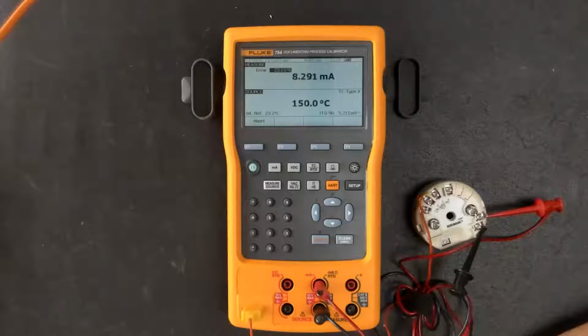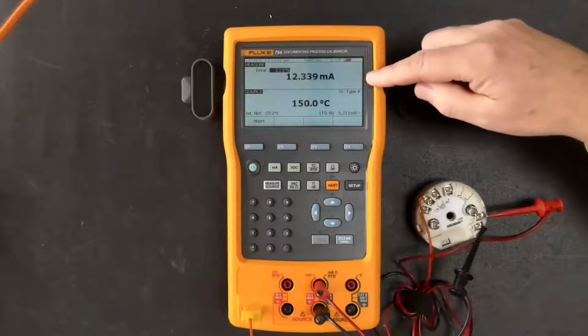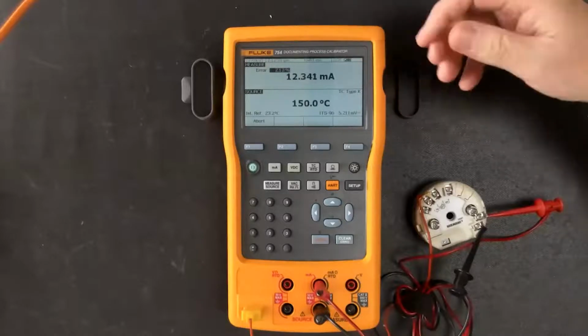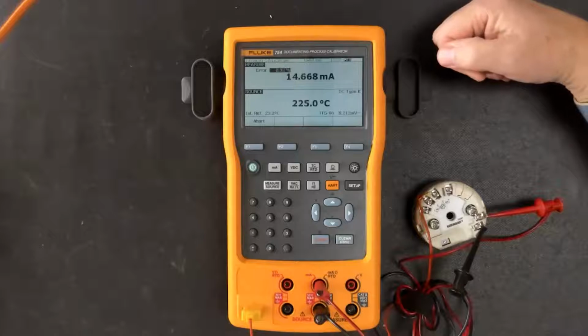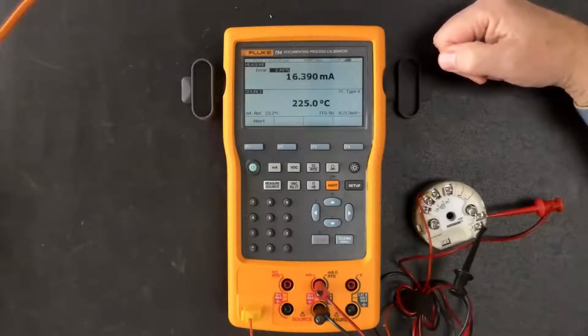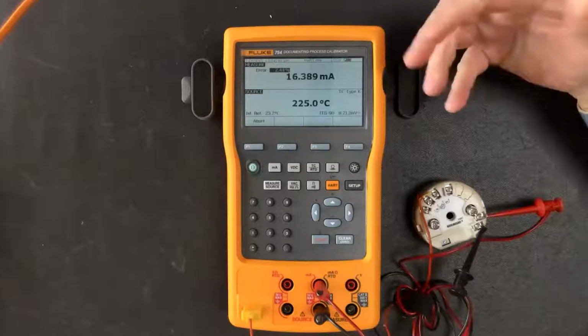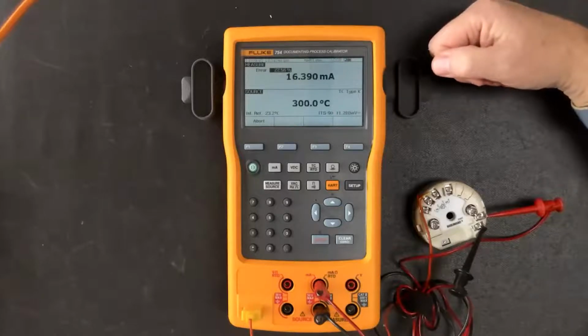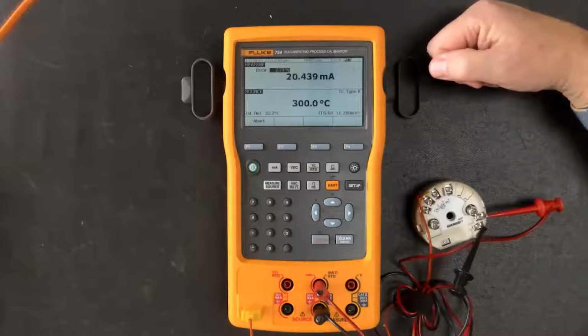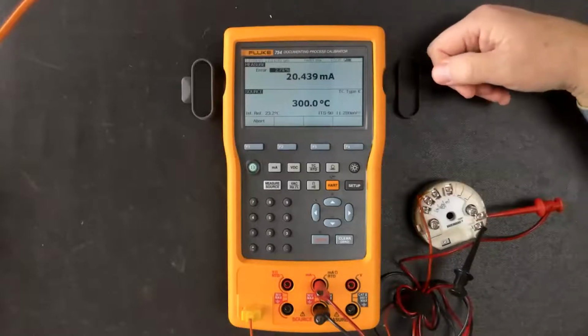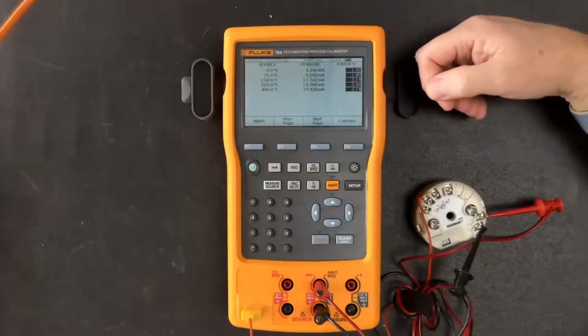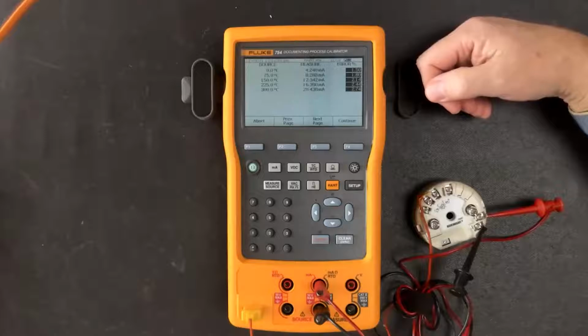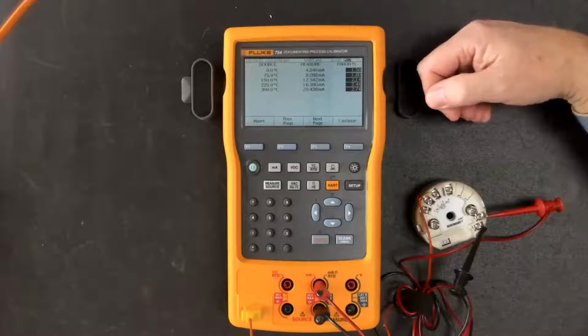And for each one of these, the calibrator is actually capturing the milliamp value for each of these test points. So none of this has to be written down. It's all automatic. It's highly accurate, and it makes life a lot easier. And I can be drinking a cup of coffee while I'm doing the calibration, so it's kind of nice. So once all the information has been captured in this calibration, this is called the as found. This is when you first bring your calibrator to the device and you connect up and take your readings. This is the as found.